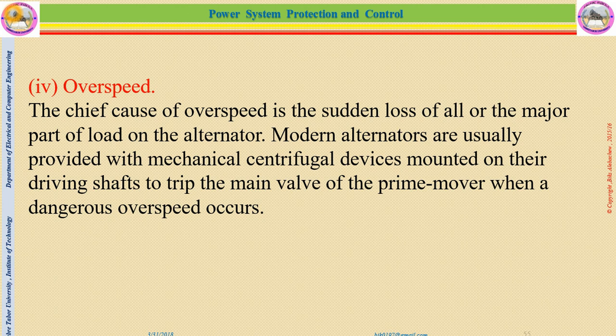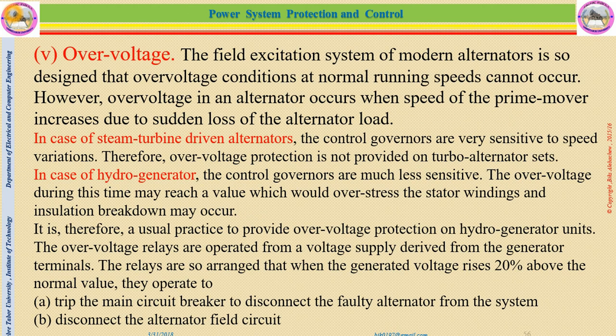Modern alternators are usually provided with a mechanical centrifugal device mounted on their driving shaft to trip the main valve of the prime mover when dangerous overspeed occurs. The other one is overvoltage. The field excitation system of a modern alternator is so designed that an overvoltage condition at normal running speeds cannot occur.